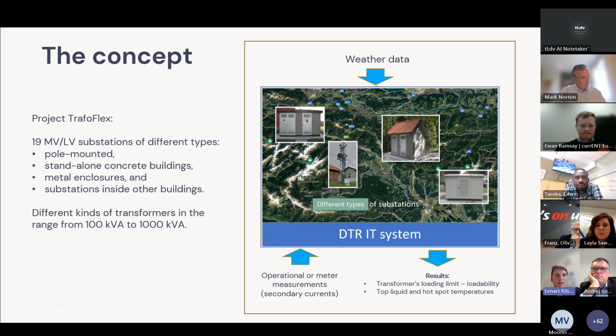For validation of our calculation, we also implemented an IoT measuring system. The IoT measuring system was developed and implemented to obtain data, as I said, for the thermal model and for the verification of the results. On the left side, you can see a picture with three white boxes. Those are the temperature sensors that we needed: one for the hot spot, one for the cold spot, and one for the temperature where the transformer is placed. Then we used the gateway to send the data to Sumo Cloud, where calculations and validations were made. So if we proceed to the next slide.